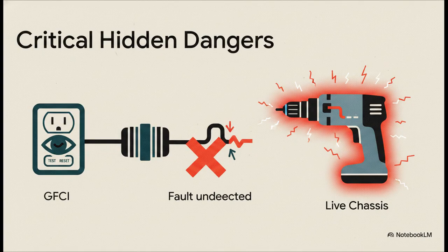And the scary part is, the dangers don't even stop there. Because the output is floating, a safety device like a GFCI on the input side is totally blind. It can't see what's happening. So if a tool you're using has a fault, its metal casing could become fully electrified, and no fuse or breaker would ever trip. You've essentially created a silent, invisible trap, just waiting for someone to complete the circuit.